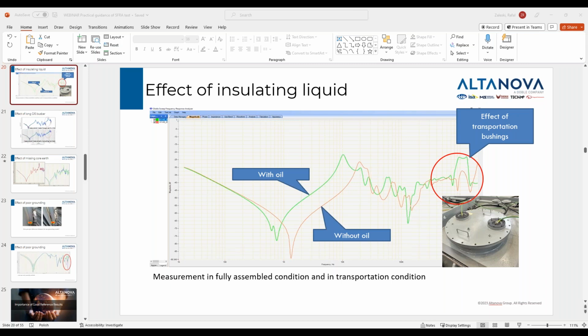Can you perform a SFRA test when the transformer is half filled with oil? That was already answered. When shorting the windings, whenever doing the trace, do you have to ground the windings as well or short the windings together only? Well, we normally short them only, but it is always important to write in your report what you actually did, because in the end you need to present your results. You have to interpret them. I think they will be equally interpretable whether it's short and grounded or not.